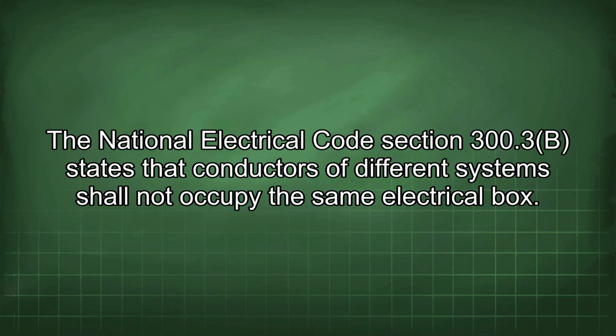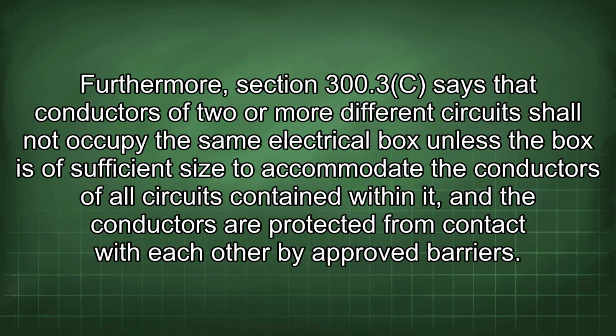The National Electrical Code Section 300.3b states that conductors of different systems shall not occupy the same electrical box. Furthermore, Section 300.3c says that conductors of two or more different circuits shall not occupy the same electrical box unless the box is of sufficient size to accommodate the conductors of all circuits contained within it, and the conductors are protected from contact with each other by approved barriers.